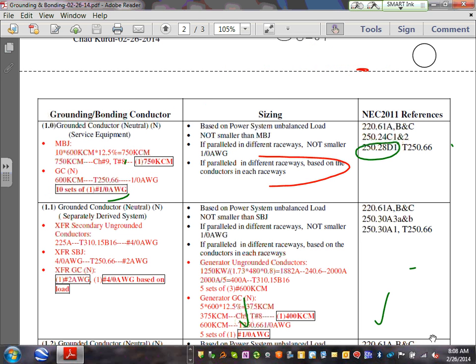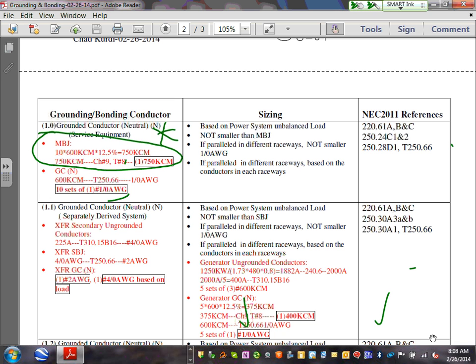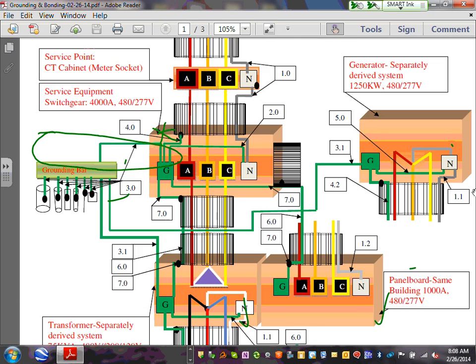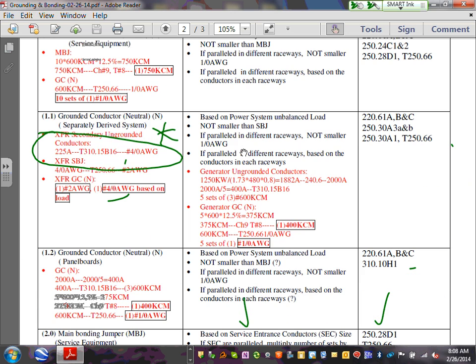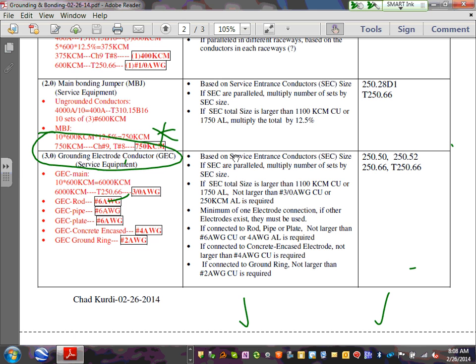Let's go to the second thing, guys, which was the main bonding jumper. I want to remind you, this is how we size the main bonding jumper, right here. Everybody can see that? The main bonding jumper is sized based on this. So the second thing that we did is number 2, main bonding jumper. If you go to the main bonding jumper, Adam, right in here. Here's my main bonding jumper.